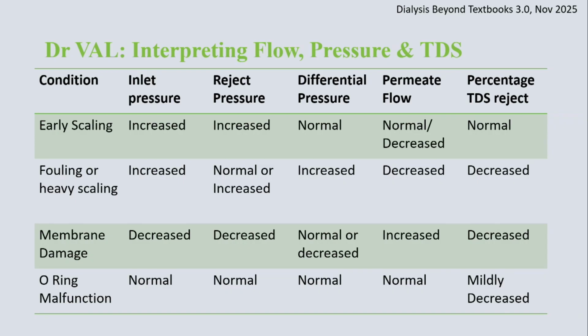And finally, there can be a mixing of the concentrate and permeate stream simply because the stainless steel housings are built by the vendor most often, and the O-rings that come are standard. So if the groove that is made for the O-ring is not perfectly cut, then that O-ring slips out of the groove and your two streams mix. In such a situation, you have a mild increase in the outlet conductivity with all other parameters being normal. Look for the O-ring. The O-ring will usually have slipped out of its seat. And you need to replace the O-ring and actually cut the groove deeper. So we faced this problem twice.